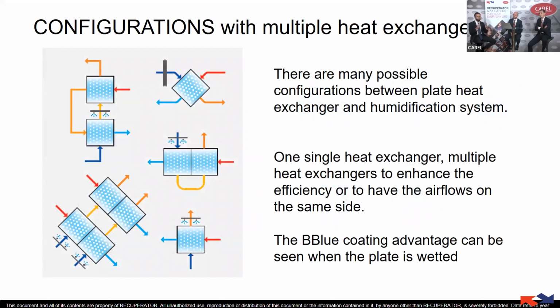We have seen just one plate heat exchanger, but we can also work with multiple combinations of heat exchangers and humidification systems. In this way we can play with one humidification system and two heat exchangers, also to have control over the direction of the airflows. But it's always very important to keep in mind that we should exploit gravity and wet the plate of the heat exchanger as much as possible thanks to the pressurized system.